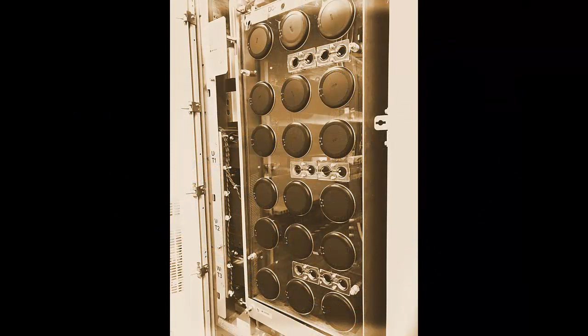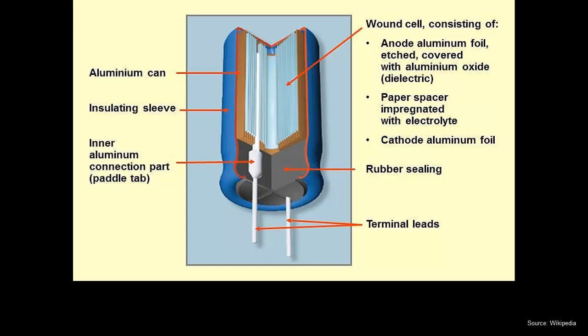When a drive is unpowered for over 1 year, it is an important step in the startup process to reform the DC bus capacitors. When capacitors are unpowered for extended periods of time, aluminum oxide forms on the insulator foil between the positive and negative plate of the capacitor. This aluminum oxide that forms on the foil is a brittle material. When this oxide cracks, a leakage current will flow between the anode and cathode.